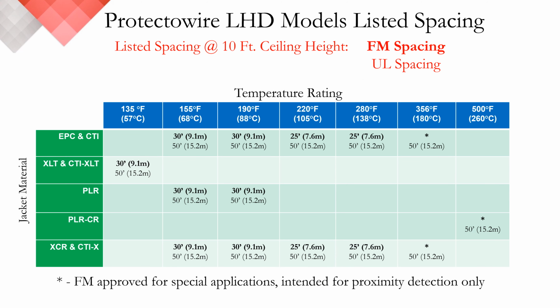Within the special hazards community, linear heat detection is a niche element, providing protection primarily in industrial settings and commonly installed to provide open area protection. Within UL and FM guidelines, it's listed in the same category as spot heat detectors with similar open area listed spacing, typically 50 feet per UL and 25 to 30 feet per FM.